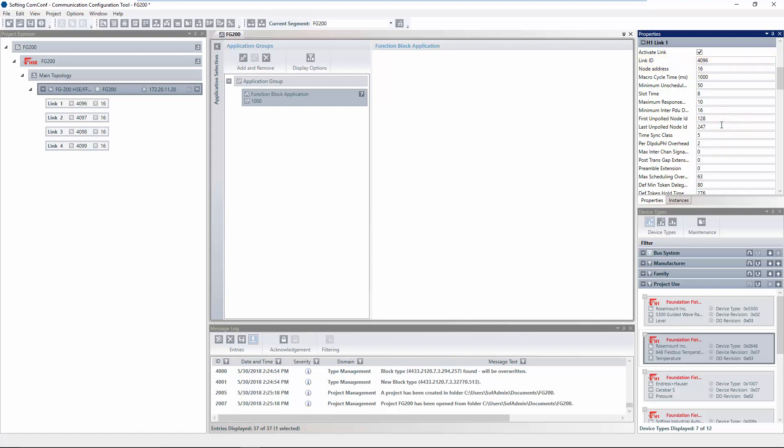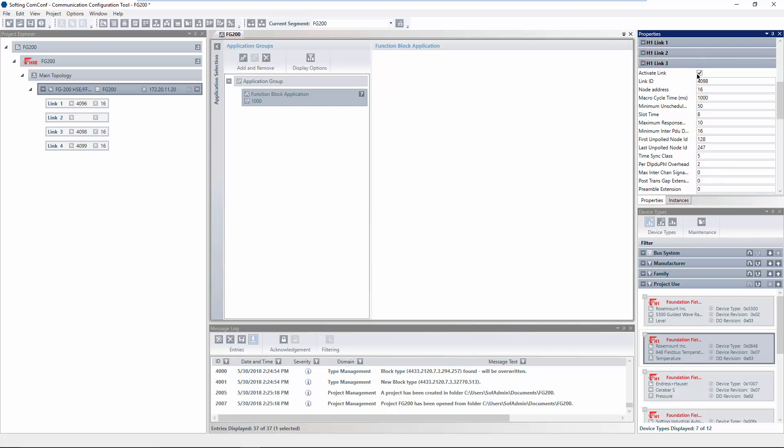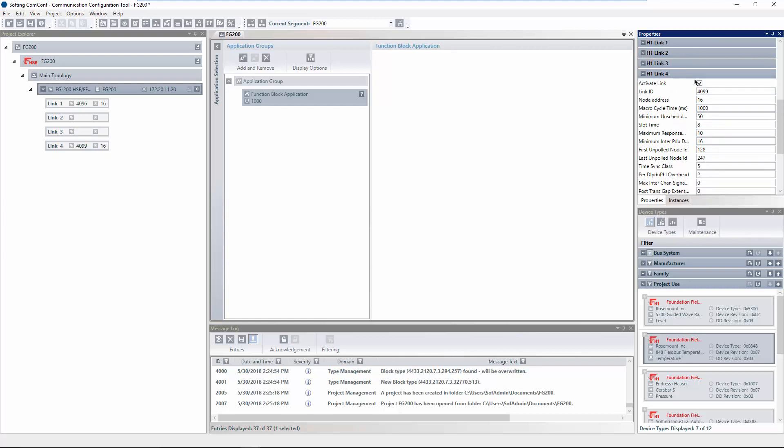adapt the link ID and the node address of the links. The address range that is considered within a link can be reduced by the parameters firstunpolledNodeID and numconsecunpolledNodeID. Devices that have addresses within this range will not be incorporated into the live list. In our example, only the first link of the FG200 is used. Therefore, we deactivate the other links.